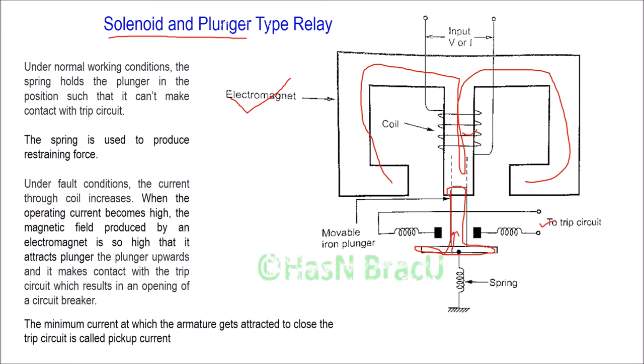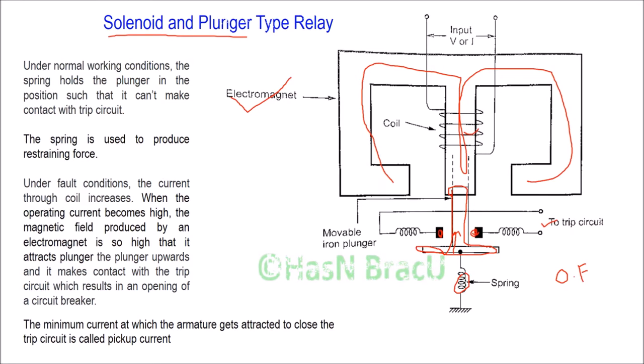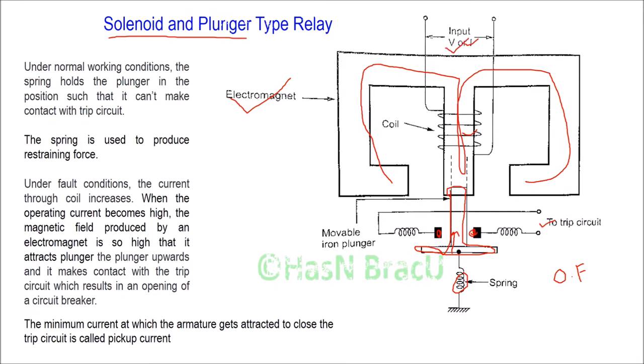This plunger must be moved upwards to make contact with the trip circuit. You can see a spring which provides the restraining force. Restraining force is the force of the spring which is opposite to the operating force. When supply is given, current flows through the coil, the coil is energized, magnetic flux is produced, and this magnetic flux flows through a closed path.